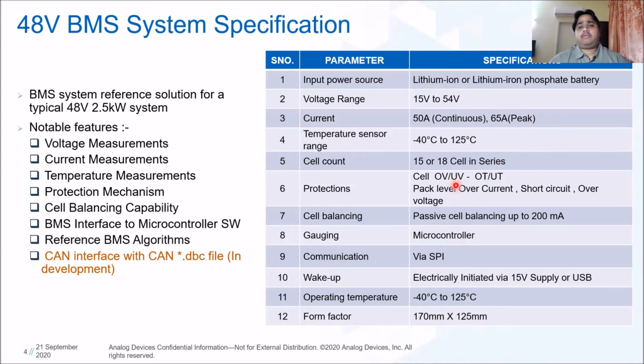At the cell level, we have over voltage, under voltage, and over temperature, under temperature control on the software side. At the pack level, we already have overcurrent, short circuit current, and over voltage protections in the system. We can balance up to 200 milliamps per cell here.